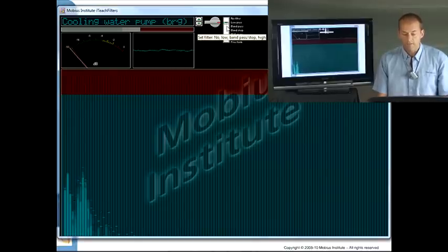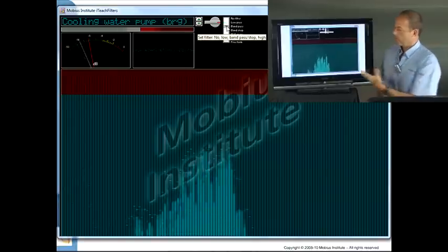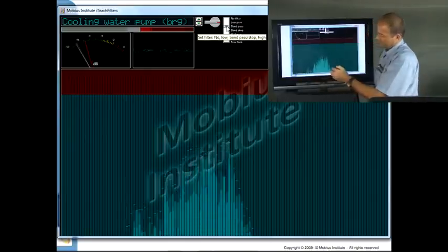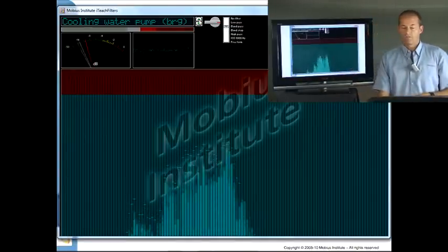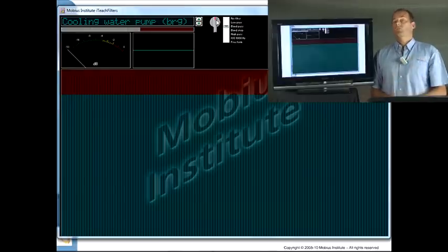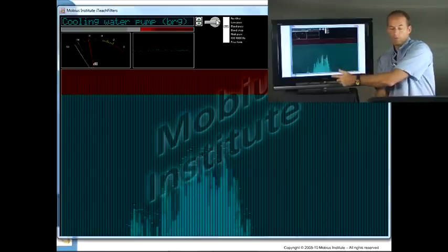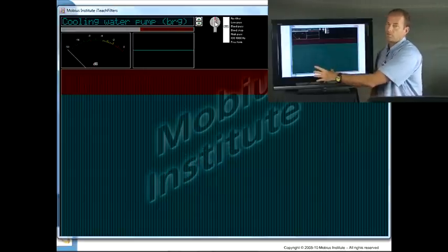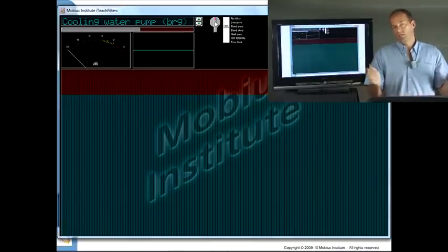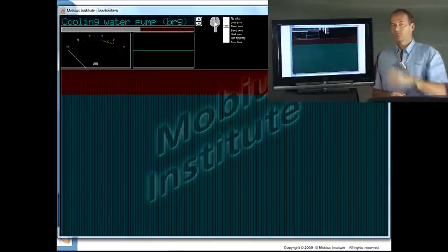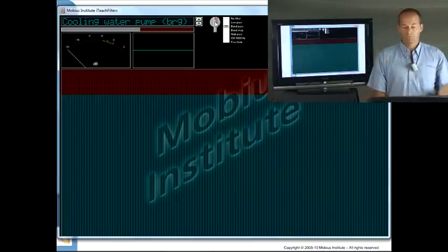Let's have a look at a band pass. So my band pass, I've blocked that out and I've blocked that out and I've let that through. So, for example, when we do set up your enveloping or demodulation or that sort of a bearing detection system, they may give you the option of a band pass filter. And all it means is you're trying to say, hey, I'm going to detect the point at which the vibration just in that band represents the bearing vibration, and outside could be other vibration we're not interested in. In particular, all that low frequency vibration could be much higher in amplitude.